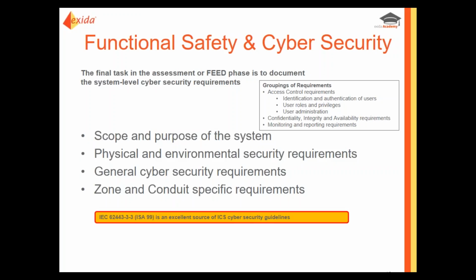If your SIS is connected to your PCN, you can allow the SIS to read data from the BPCS and even write data out. You could allow the BPCS to read data from the SIS but not write back to the SIS. So you can control how data flows.